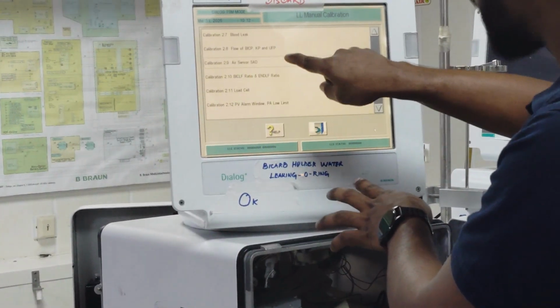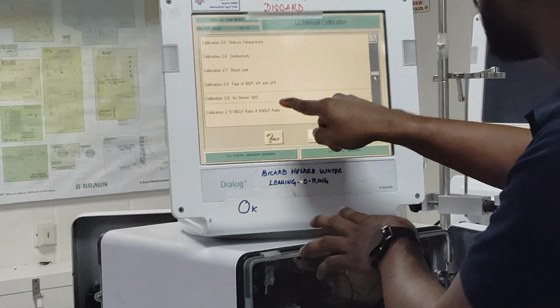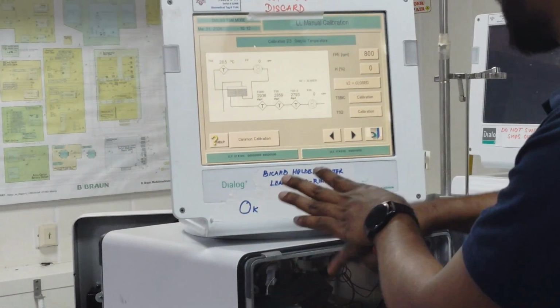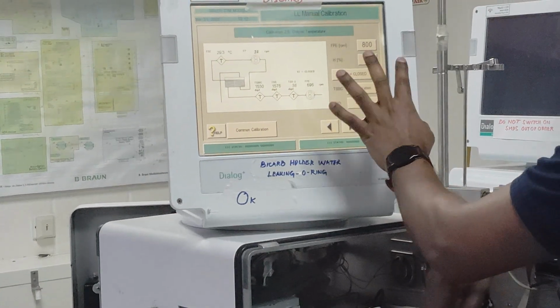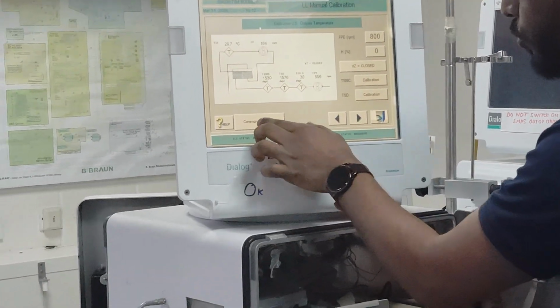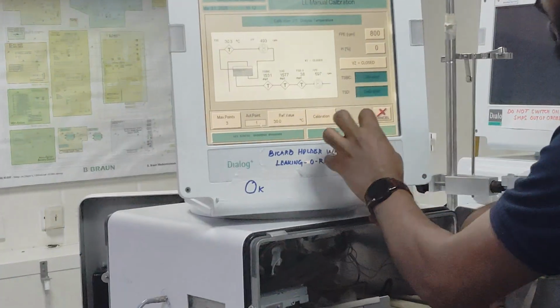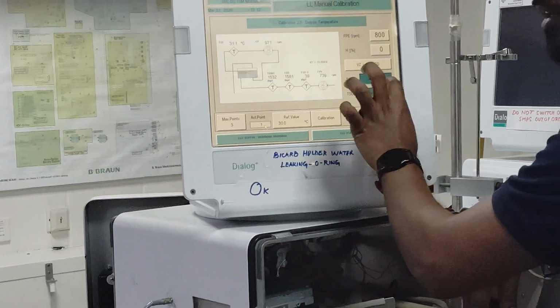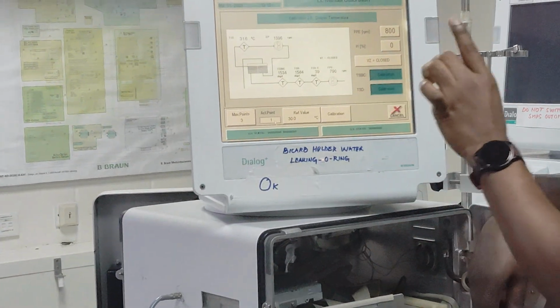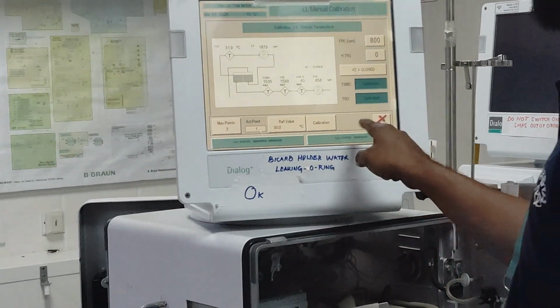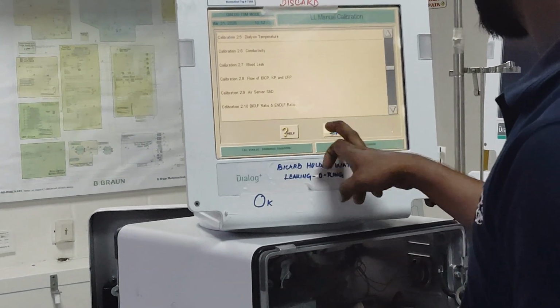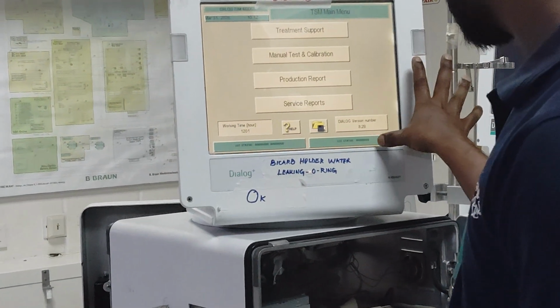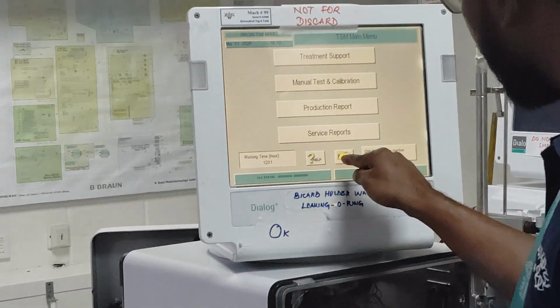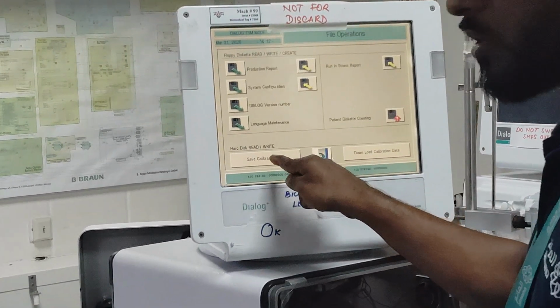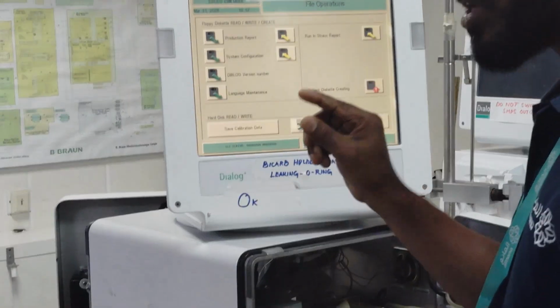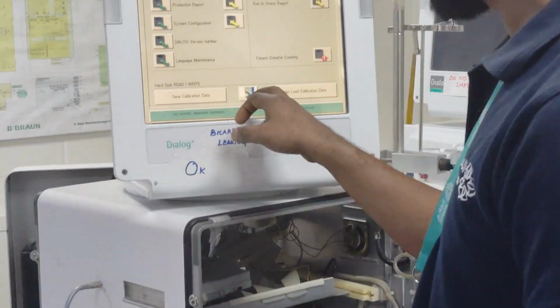Now the other things you are calibrating. Suppose you are calibrating temperature. Now you don't see any saved calibration data here. After you start the calibration and all three points are calibrated, after the calibration is complete, this will appear there: save calibration. Only at that time will it appear, so at that time you have to save. After the save is completed, you have to come back again here to the last option. Here you have to save, if your calibration data are correct. If wrong, don't save here.